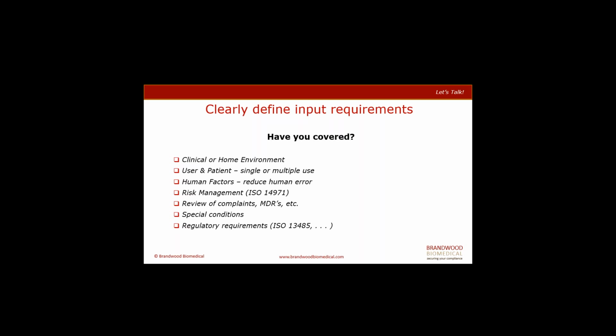And if multi-use, does it require re-sterilization or perhaps reprocessing? Have you looked at the human factors, specifically to reduce human error? If it's a fairly complex device or has an interface, such as a GUI, how easy and understandable is that particular GUI to use? Risk management.